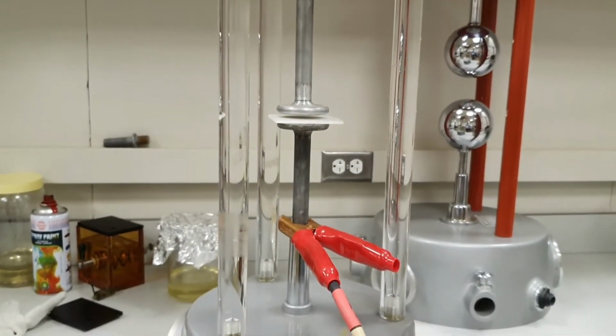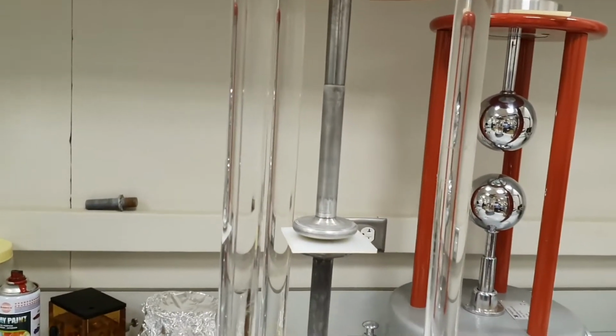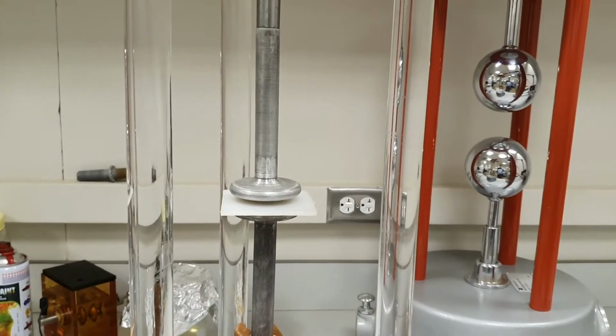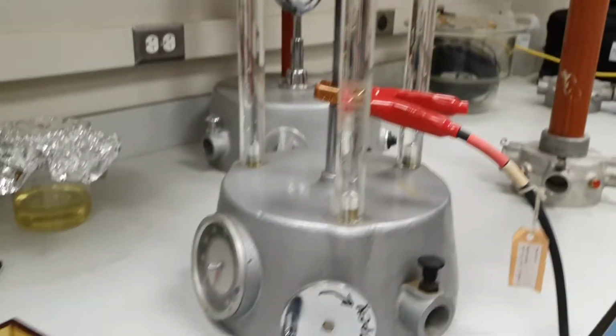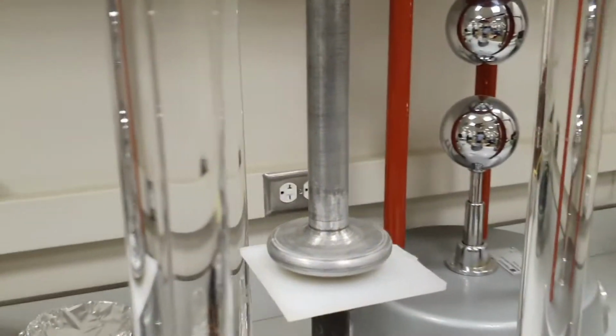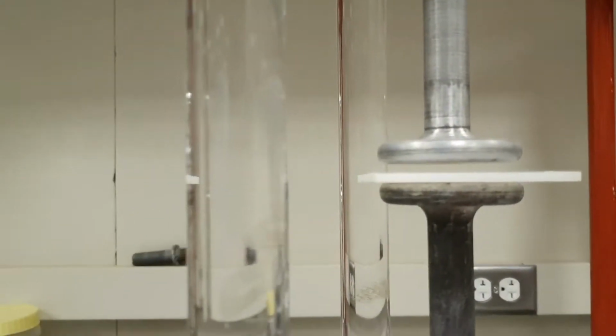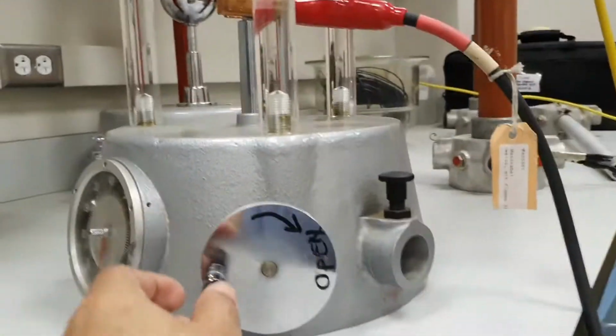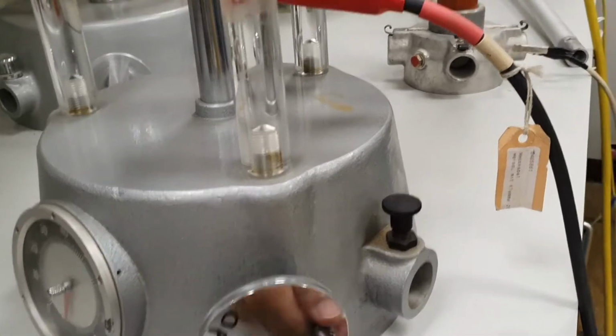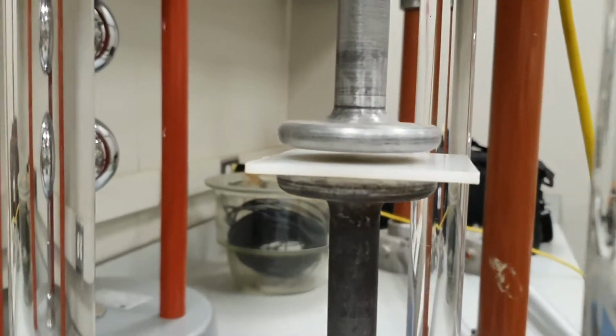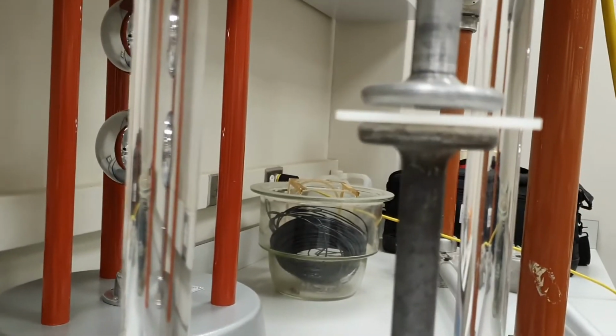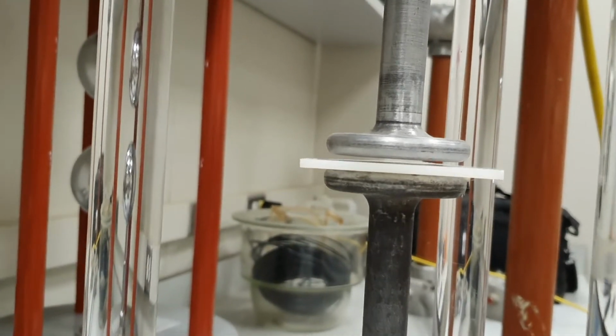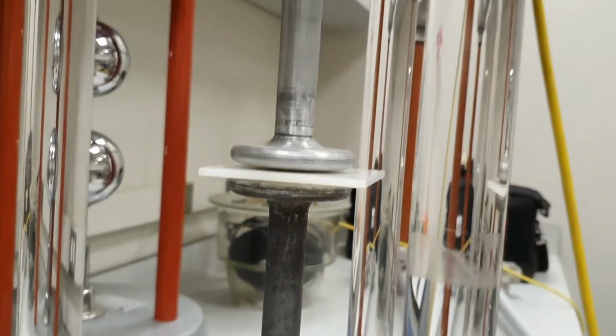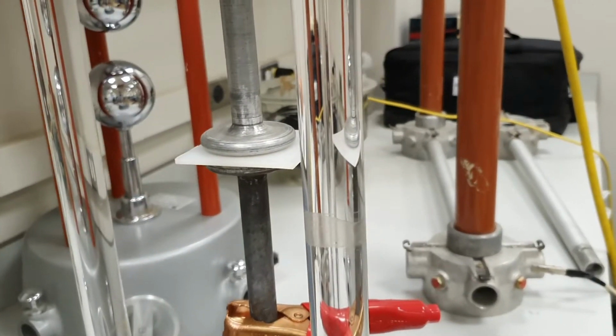You will place the XLPE insulation between these two plane electrodes, making sure the electrodes are touching the insulation properly. There is a wheel rotating handle to make this tight. As I tighten it, you'll see the gap coming closer, making sure the electrodes are sitting tight on the insulation.